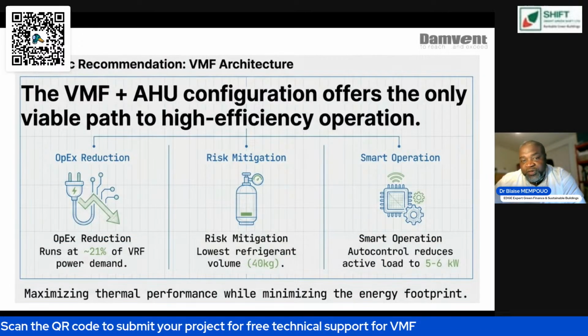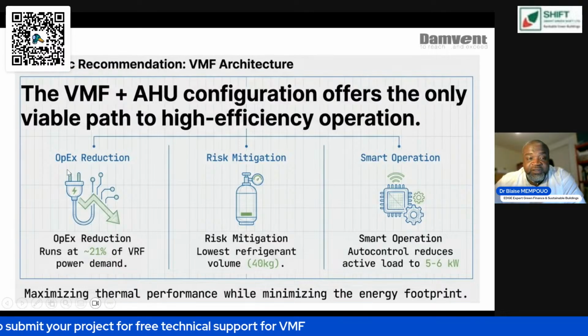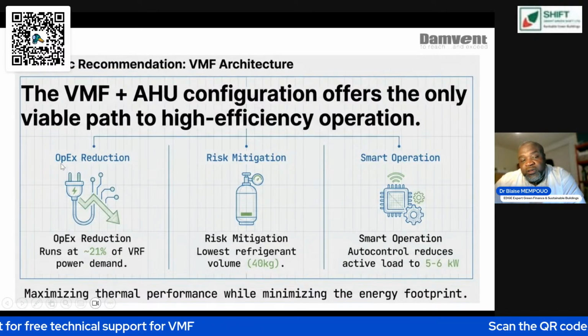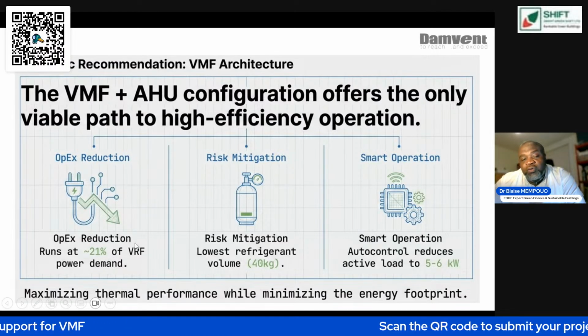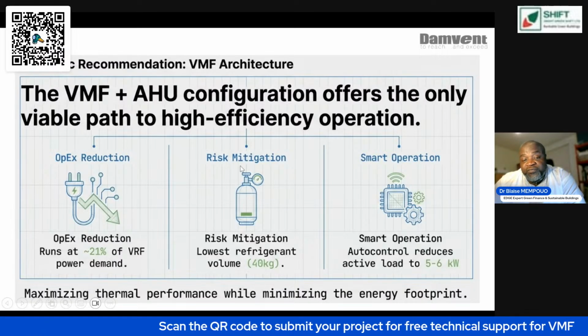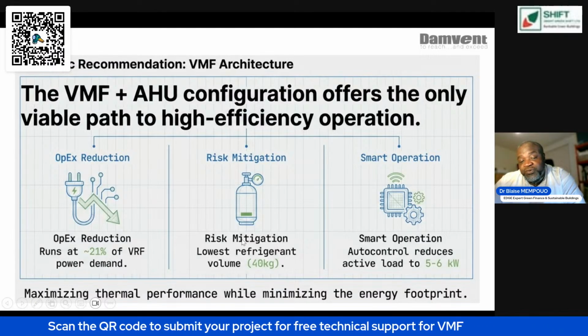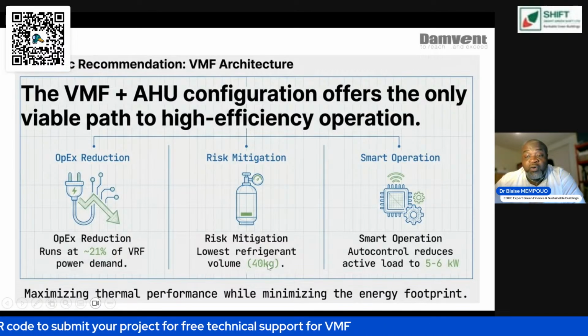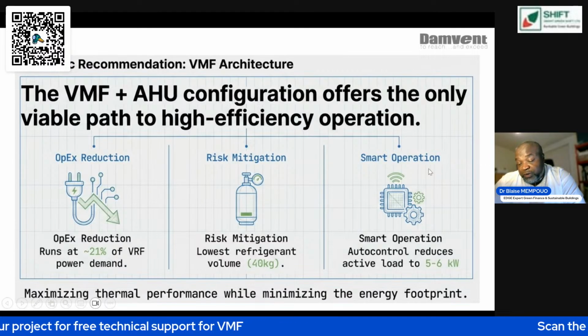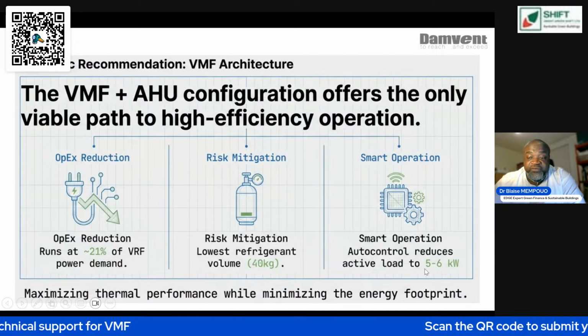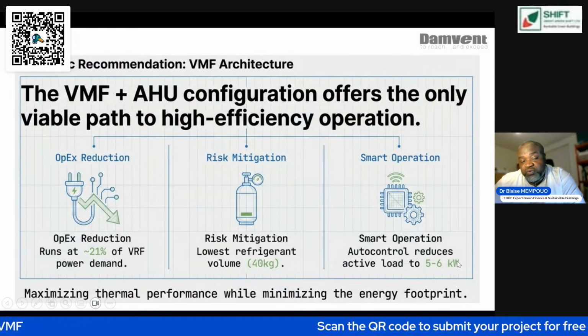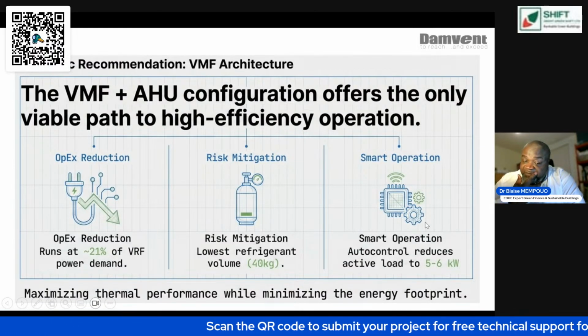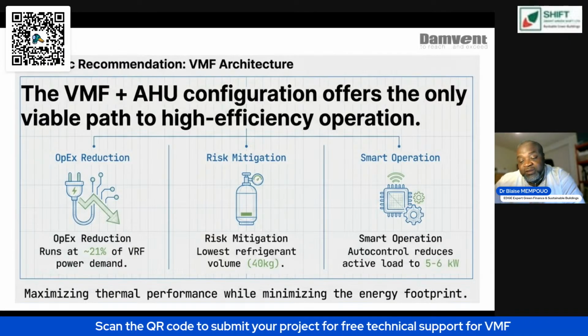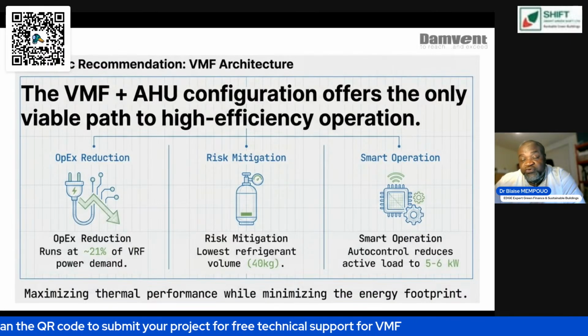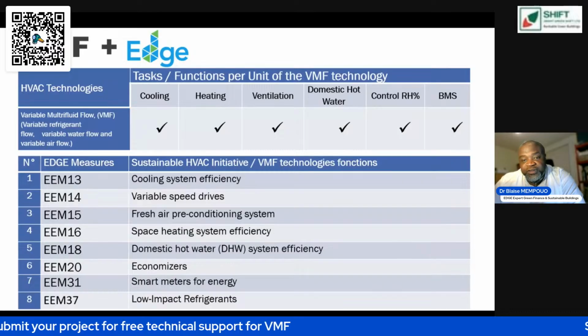The kind of strategy recommendation to finalize everything: the OPEX is very low compared to the alternatives, a minimum of 21%, even greater. And in terms of risk, because there's no refrigerant inside the buildings—the low refrigerant, all 40 kilogram, is outside—and with the smart operation I mentioned, saving 5 to 6 kilowatt, that maximizes thermal performance while minimizing energy footprint. That's a huge advantage over conventional systems.